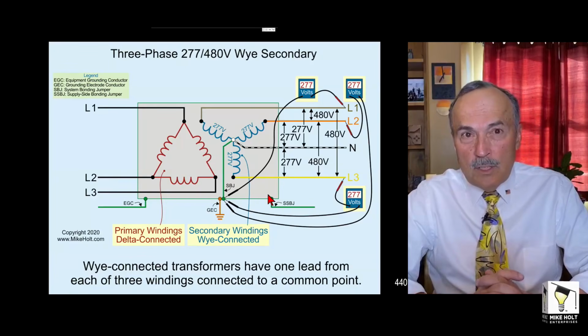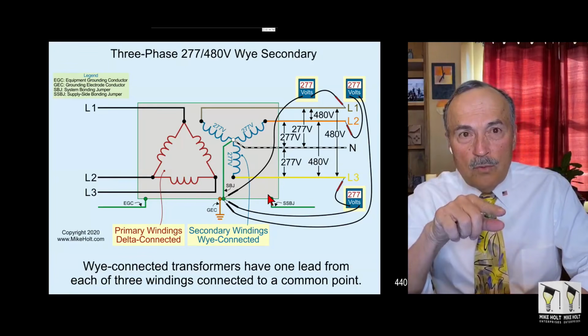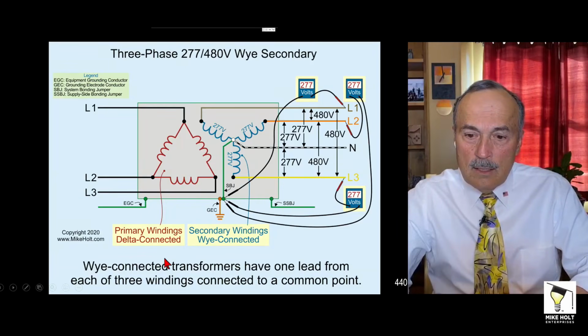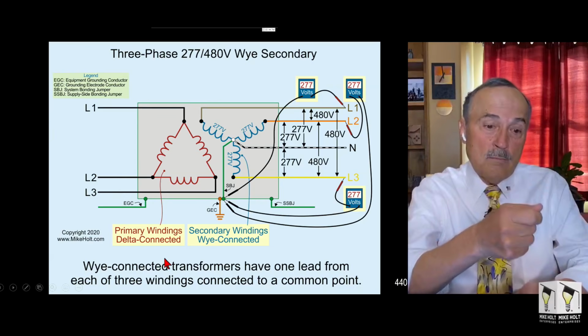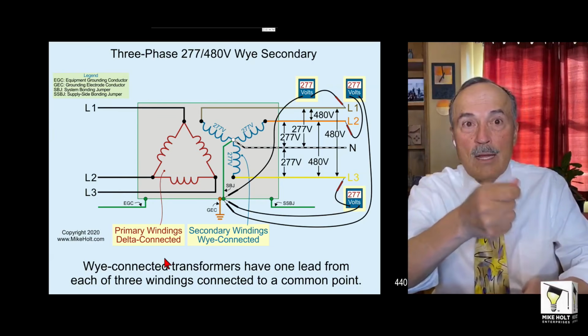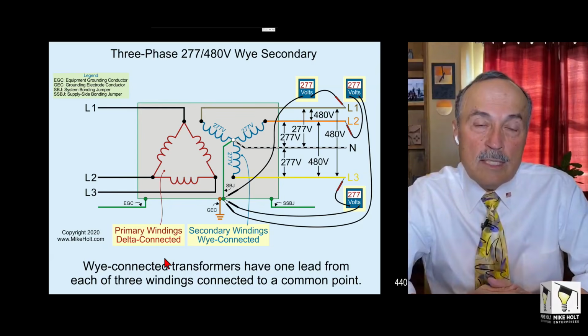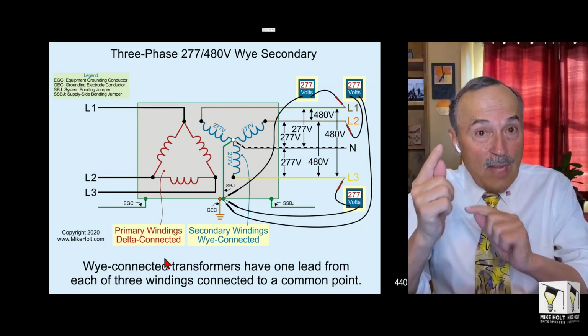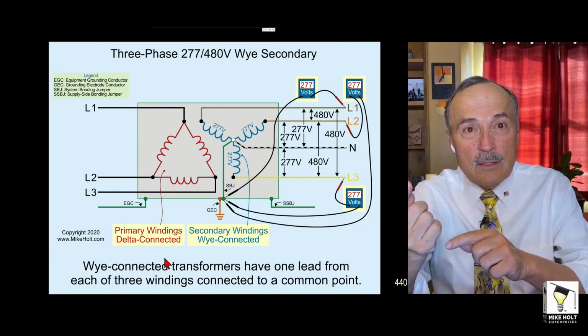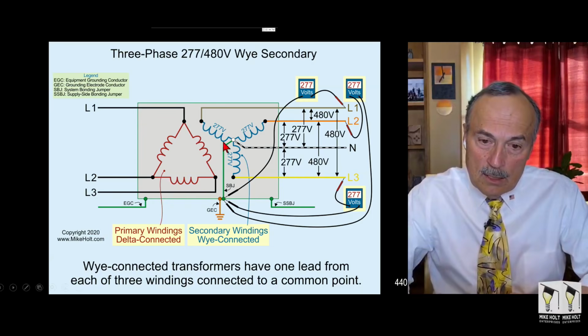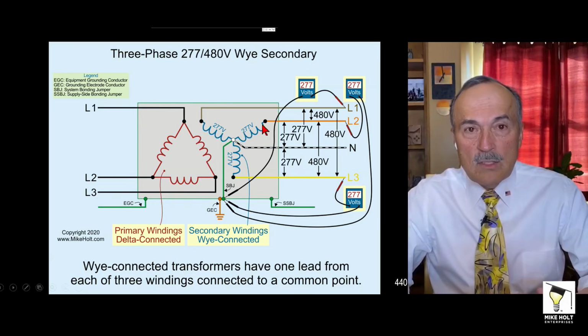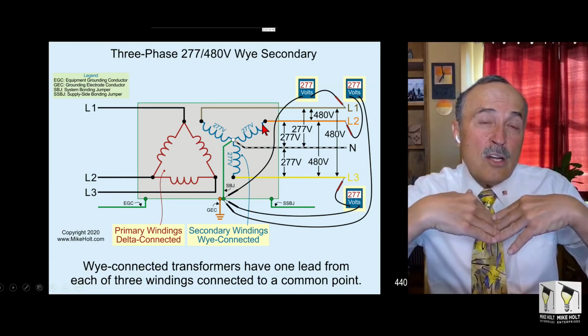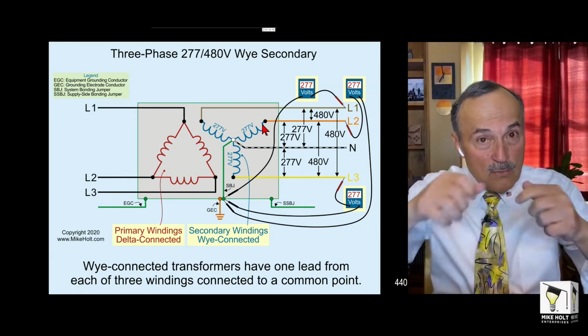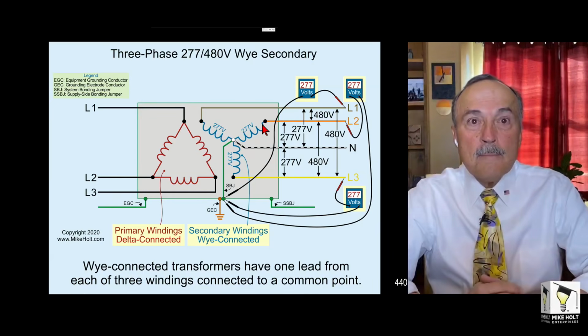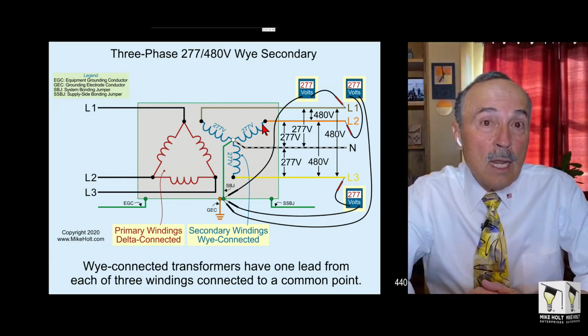Let's talk about the voltages. Line to neutral voltages are 277, right? And line to ground, because neutral is bonded to the case, well, then line to ground and line to neutral at the same points are going to be 277. Between two phases, or between two lines rather, it's going to be 480, because it's 277 plus 277 vectorially added at 120 degrees out of phase with each other. And if you put a meter there, as we talked about, 480 volts, line to line.